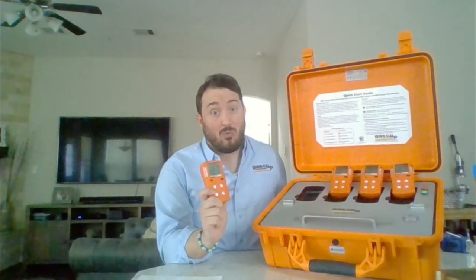It has a built-in logging system that stores 25 bump tests, 25 events, and 25 calibrations, with a continuous data log that holds two months of data. This unit is a disposable detector with a battery life of 1,095 continuous days and has a three-year warranty. Along with the approved technology and the warranty, this unit is perfect for any of your gas detection needs with a limited cost of ownership.